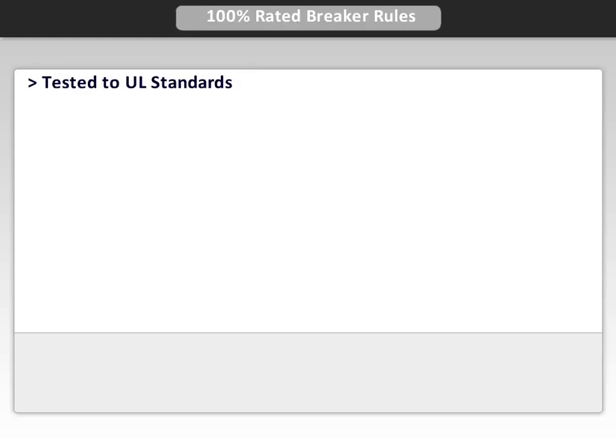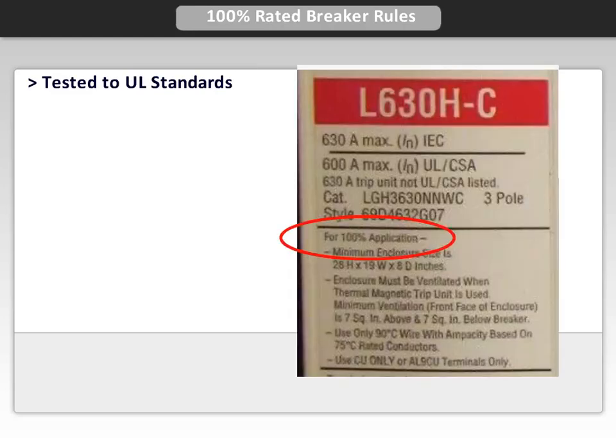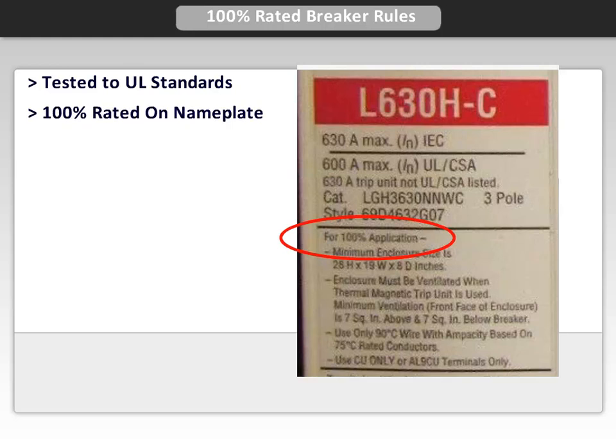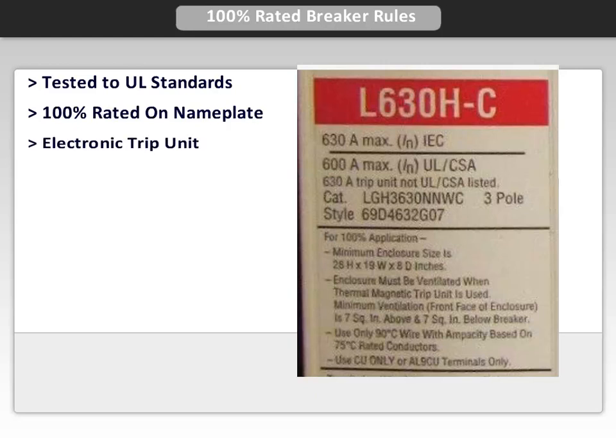There are a few rules to abide by when applying 100% rated breakers. The first is that the breaker must have been tested to UL standards. Next, 100% rated needs to be clearly stated on the breaker nameplate. The circuit breaker must also use an electronic trip unit.